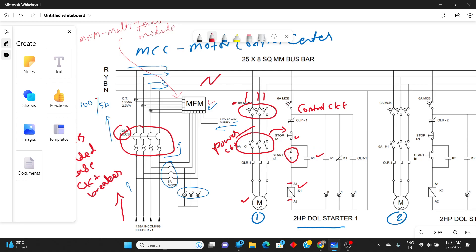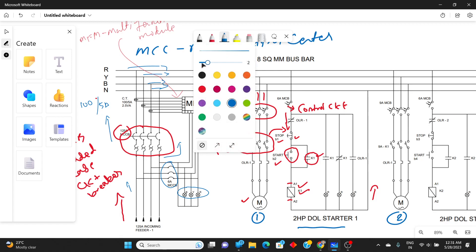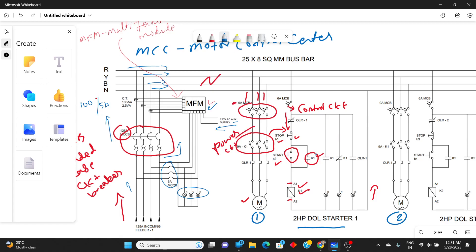If the circuit breaker is closed and we press the start button, it will be closed, so power will flow and return to neutral. Contactor K1 will be energized and closed. The auxiliary contact is connected in parallel to the start push button. Push button 1 is our stop push button and push button 2 is our start push button.